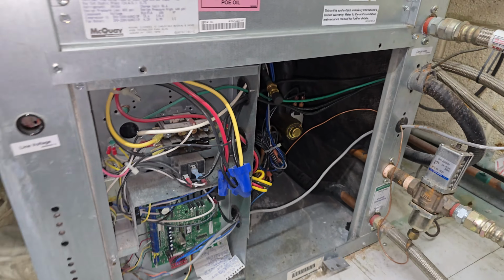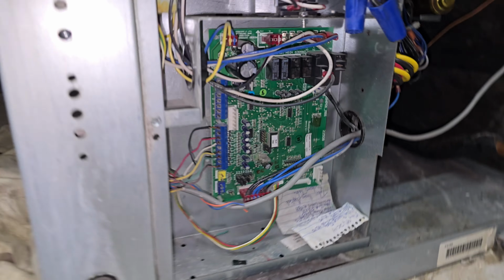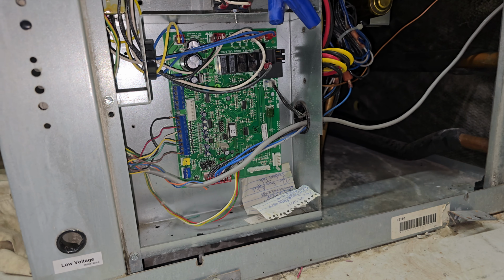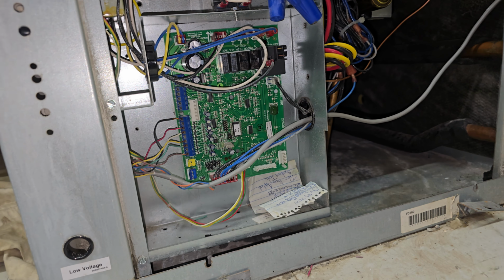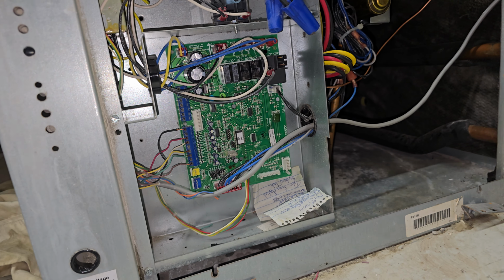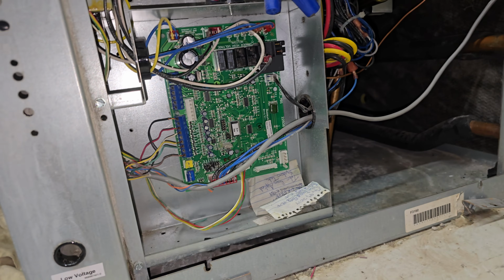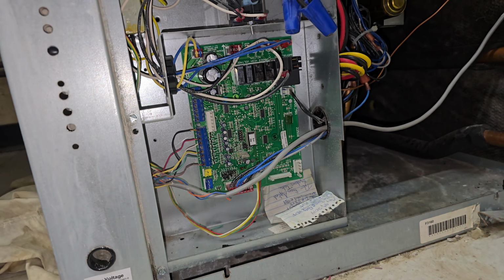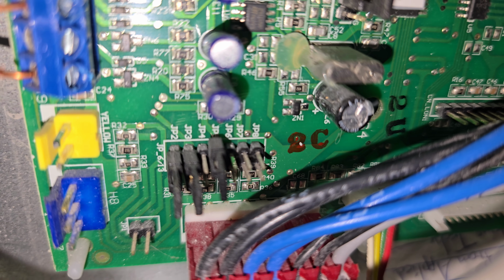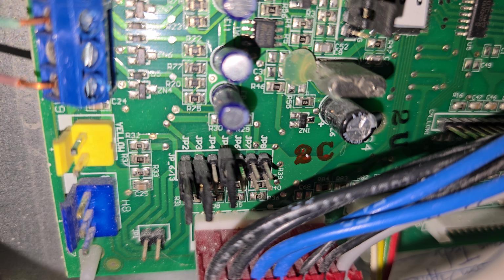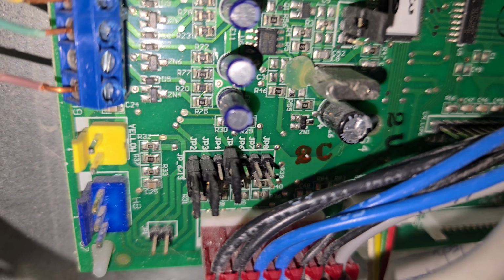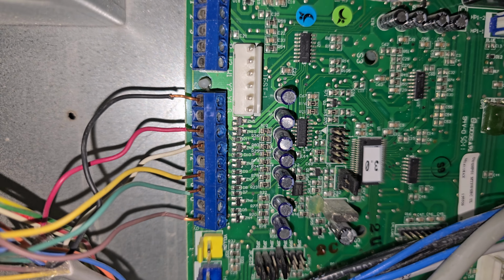Okay, so my findings so far, a couple of things seem to be happening here. This unit is sensing that there is a temperature sensor, but they don't really have a temperature sensor. What controls this unit is a thermostat. You can see there are switches here, with jumpers and no jumpers. So I took out one of the jumpers just to check if that could be the problem, but it's not.